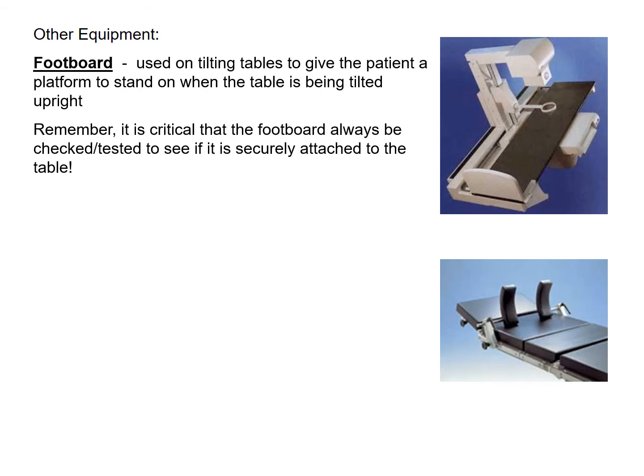Other types of equipment, of course, some tables, especially in fluoro, have a footboard. These are used on the tilting tables to give the patient a platform to stand on when the table is being tilted upright. Remember, it's critical that the footboard always be checked and tested to see that it's securely attached to the table. You would not want to not have the locks fitting correctly. The patient is sliding down, standing on the footboard, and as the table's coming up, the footboard falls off and your patient starts to slip. That wouldn't be a good situation.